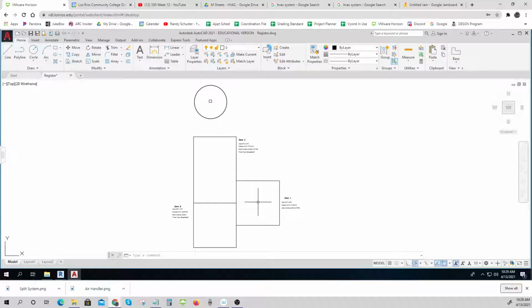And so if I've got 6 air terminals and let's say each air terminal costs me $25, but it costs me $75 to put it in, I've essentially got $100 per air terminal, and that would be $600. If I have one big air terminal and maybe it costs me $100, it's still only going to take me $75 to install it. So now I'm only paying $175. So there's always a balancing act, and that's design.